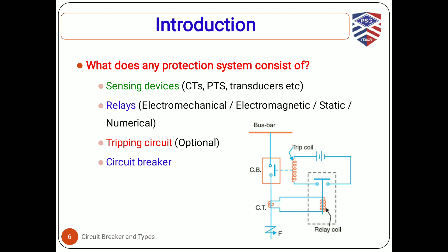As you can see from the diagram shown below, the current transformer, mentioned as CT in the diagram, is the sensing device, which senses the current and gives a signal to the relay coil. If that relay coil is energized, that will close the tripping circuit, which is connected with the battery circuit there. That tripping coil, once it is energized by the relay coil, will initiate the breaking operation through the circuit breaker. So this particular system overall is called the protection system.